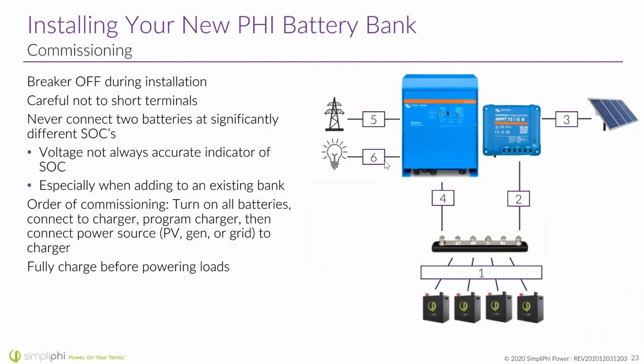Note that when you're first connecting the batteries, they'll probably come out of the box around 52 or even 53 volts, appearing fully charged. This is because the last thing that happens before they're shipped is they get charged to 20 to 30% state of charge. This is as high as we're allowed to charge them before they reach the customer, since we're not allowed to ship batteries fully charged due to transportation safety rules.